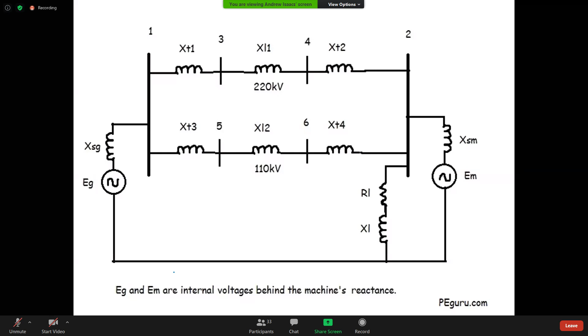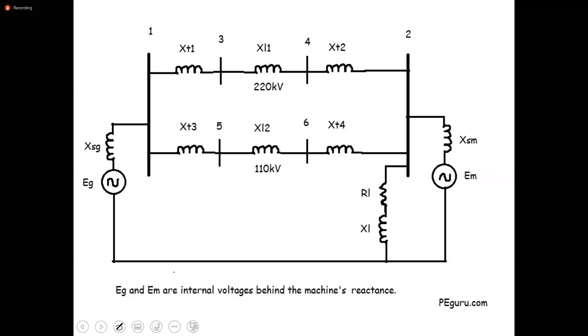So if we're doing calculations, for example, on our single line diagram, based on what I'm showing here, we'd have to always bear in mind that moving from one side of the transformer to the next, we are going to have issues with respect to the change in currents. So it could not be just a simple analysis using the reactances as we have them. Now, to solve this problem, we use a system known as the per unit system. We mentioned that the main purpose is that we have a system which helps to simplify the network with respect to the transformers.